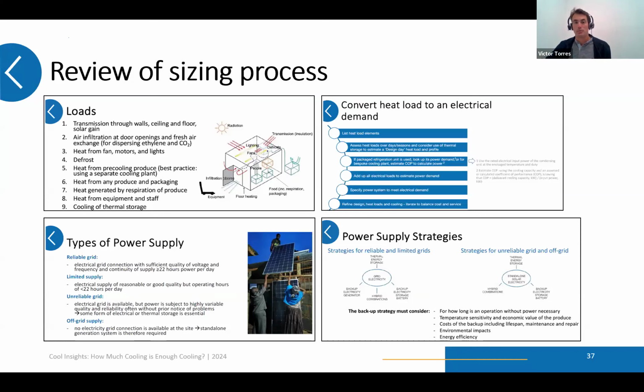The next step, which I'd like to focus on, is how to convert this cooling demand into electrical power. This is exciting because the cooling demand is thermal energy, and it needs to be converted into electrical energy by a cooling system. We're talking about vapor compression heat pumps that pump heat from inside the cold room to the outside with a certain efficiency, described by the coefficient of performance, COP, which depends on both ambient temperature and cold room temperature. So ambient temperature affects thermal losses but also the COP of the cooling unit, meaning overall energy consumption of cold rooms is very affected by ambient temperature.